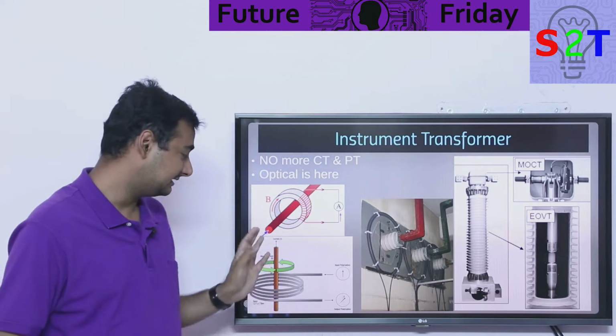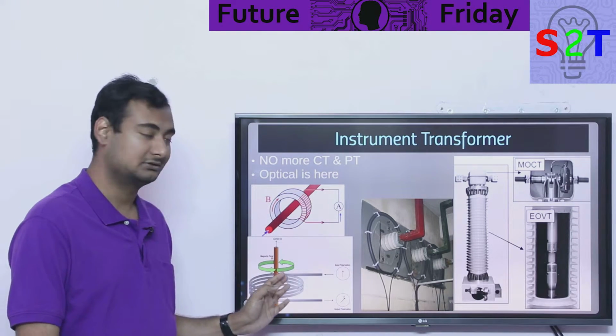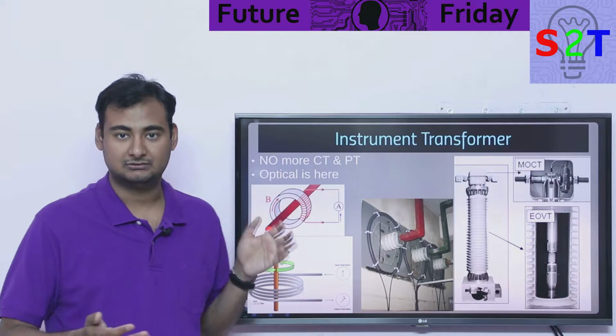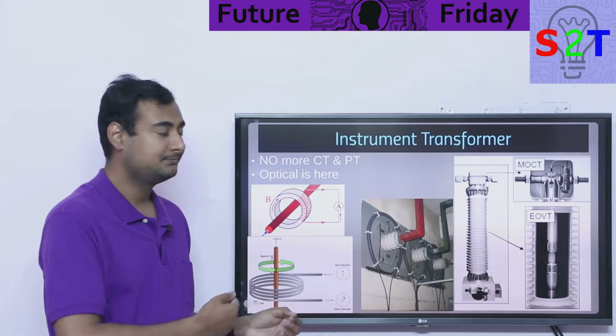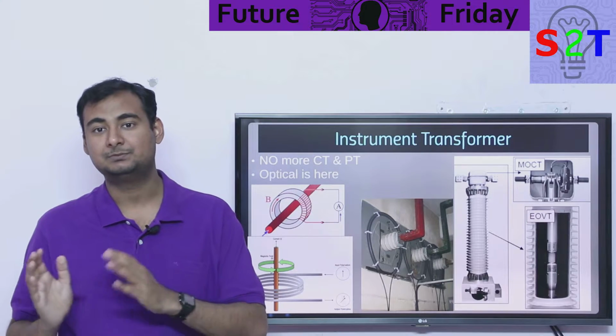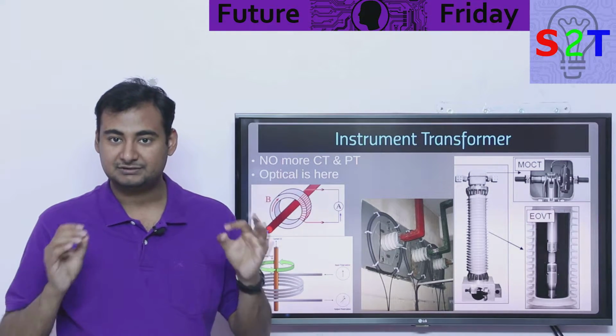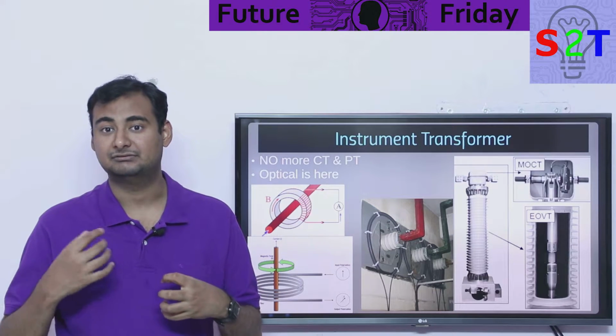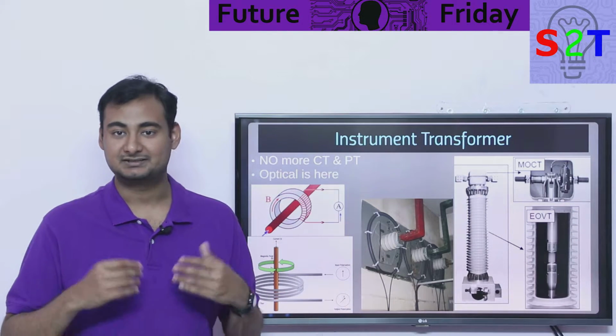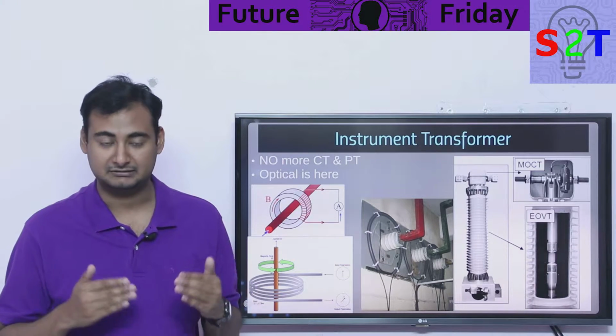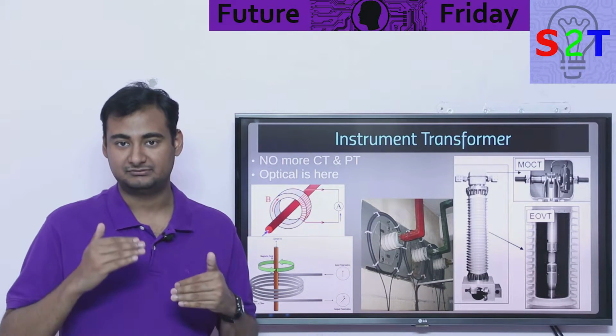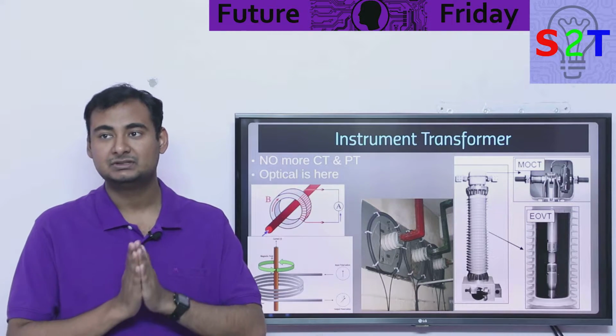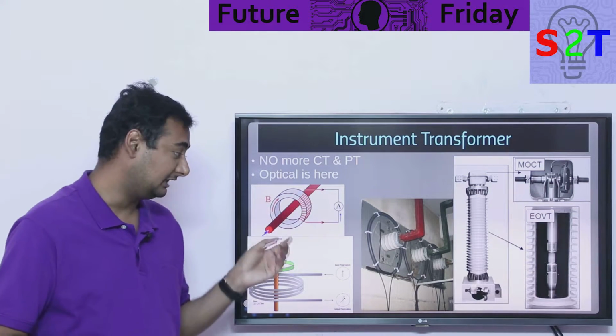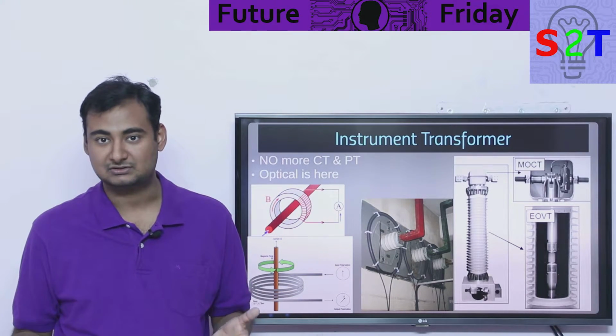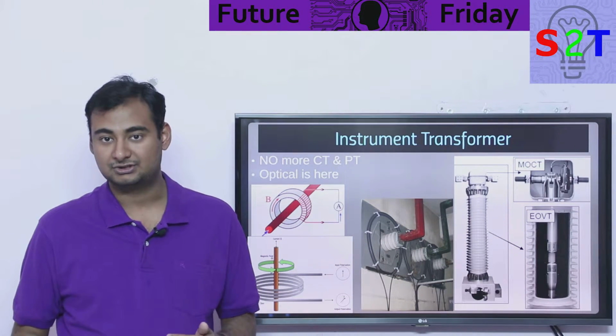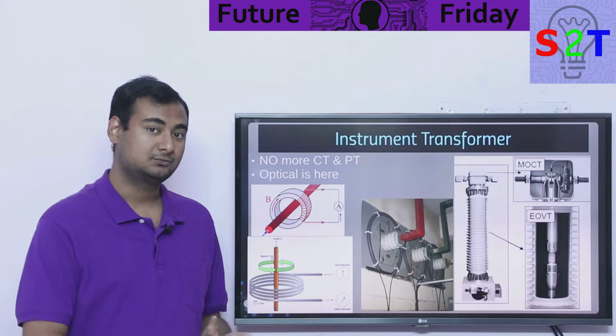In terms of voltage, that handles the phase shift, handles your amperes. For voltage there are two ways: one similar to this, and another using what we call a piezo system. Your optical fiber will have certain crystals that change based on the voltage, the magnetic field around it - like when electricity causes mechanical movement, it's the same thing. Electricity induces a physical change into the optical path, so the fiber becomes either translucent or opaque, and that way you can measure the voltage without touching the main line and without putting much load.